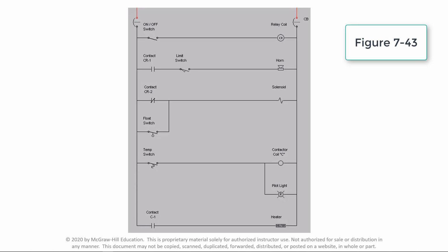Outputs are load devices that directly or indirectly carry out the actions of the input section. The output section provides the action and includes contactors, heater units, relay coils, and indicator lights, horns, and solenoids, as shown in the simulation. A combination of input devices that either manually or automatically sense a condition and the corresponding change in condition performed by the output device make up the core of motor control.